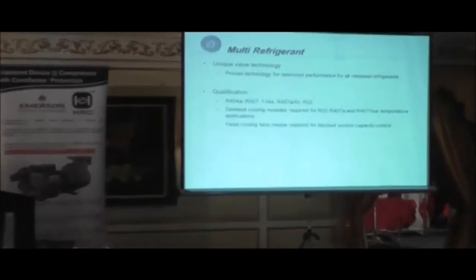As I mentioned before, with all the new refrigerant regulations that are going to be coming into the kingdom, I think from 2015, we have to make sure that our compressors are compatible with these new refrigerants. Depending on how the market is going to go, either switching to 404A, 507, or 407A for low temperature, and maybe 134A for medium temperature, these compressors have been tested and qualified for that. So when the transitions happen, you will have product ready to support that transition with your customers.